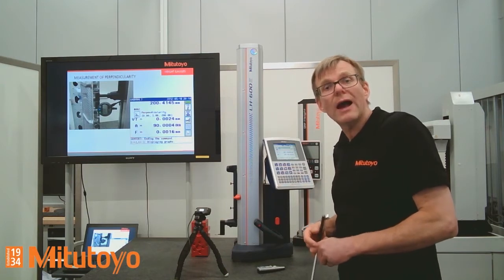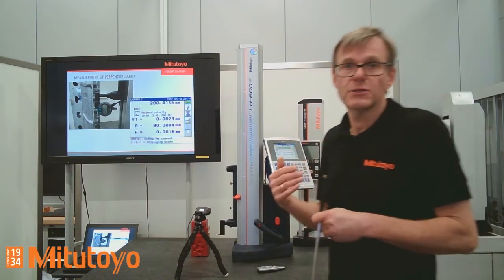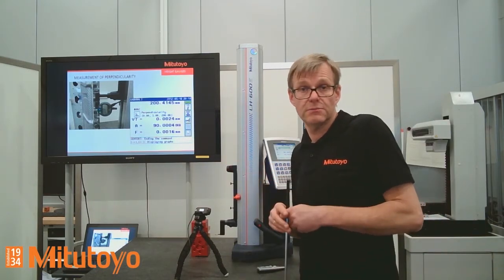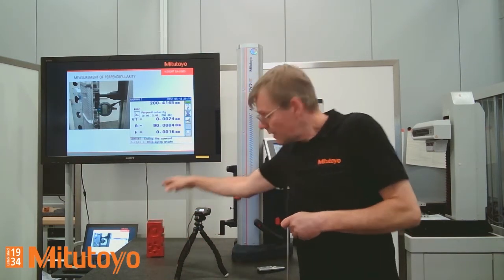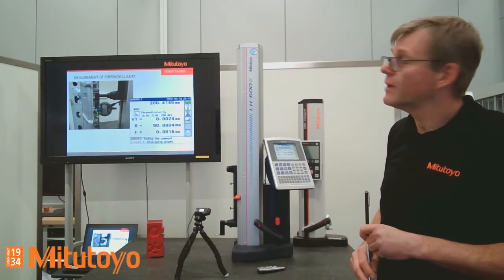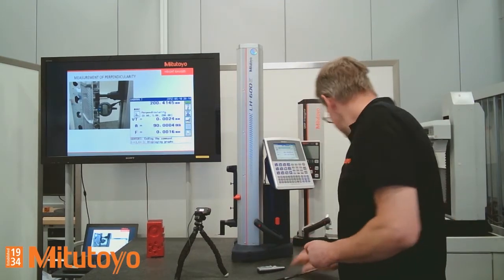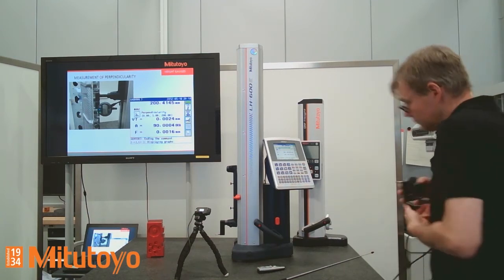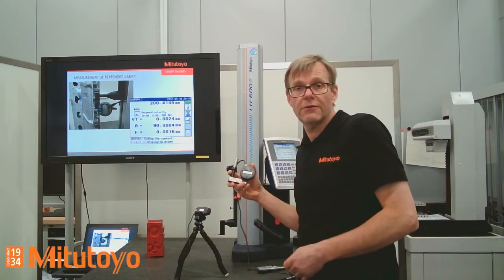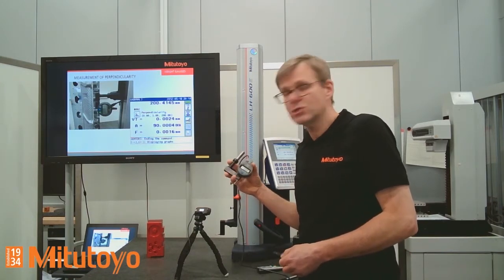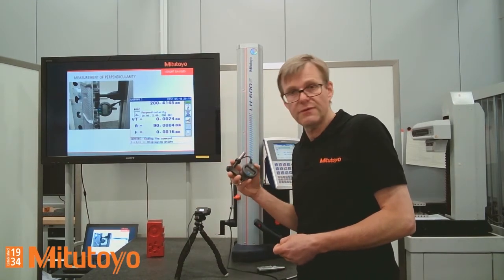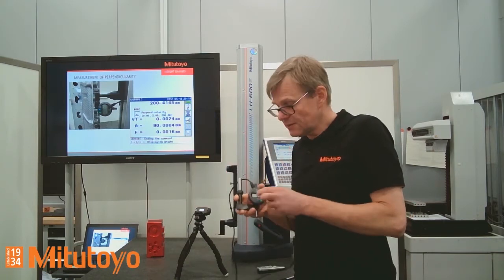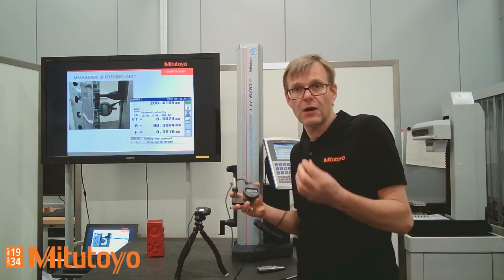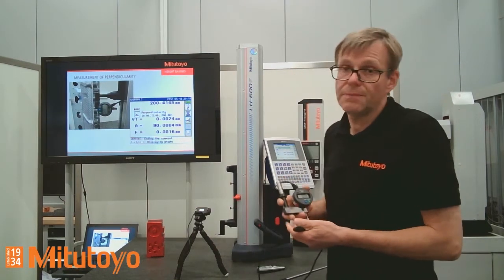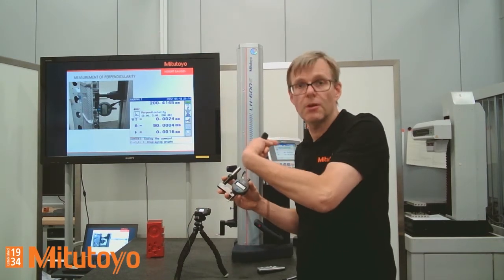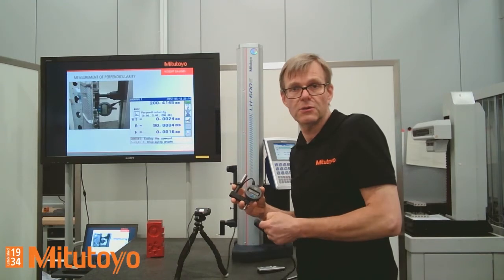Yeah, the next step, I would like to show you how to do perpendicularity measurement, because sometimes a customer would like to know perpendicularity or straightness of a workpiece. For this, I would like to change the probe, because we need this probe with the integrated digital indicator. This is a probe here, and you can see this is an ordinary Mitutoyo digimatic indicator. The digital step of this one is 1 micron, and you can use this very easily. You can use another one, it doesn't matter. Important is that there is a digimatic data output, and you have to connect this digimatic data output to the controller box of the linear height, because the measured value from the indicator goes to the controller box, and the controller box uses this result to calculate perpendicularity or straightness.